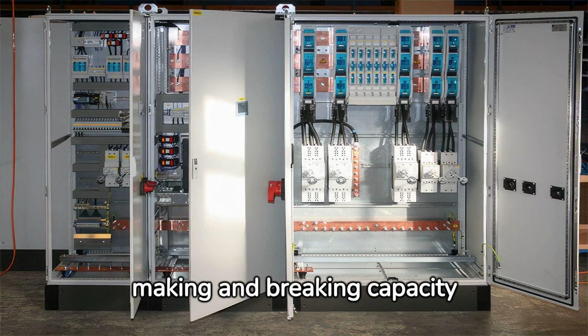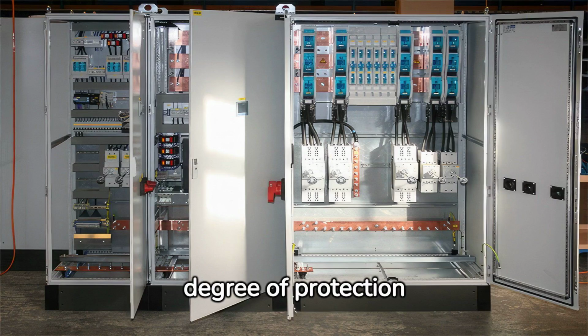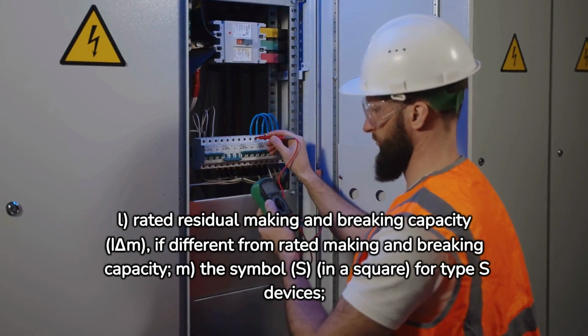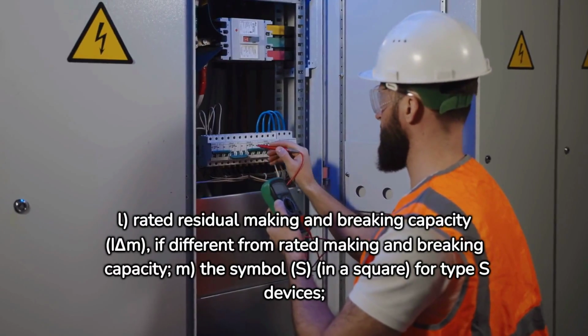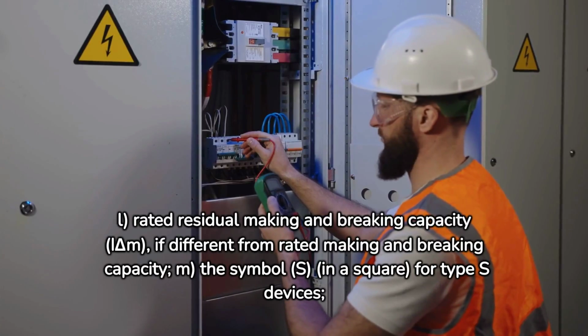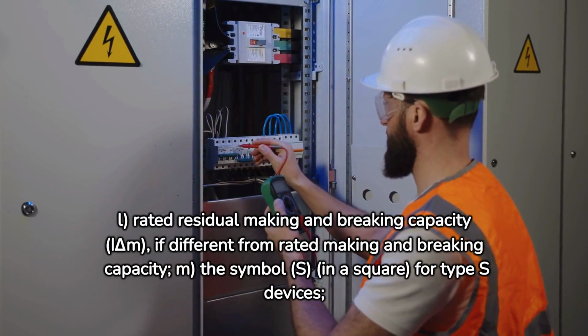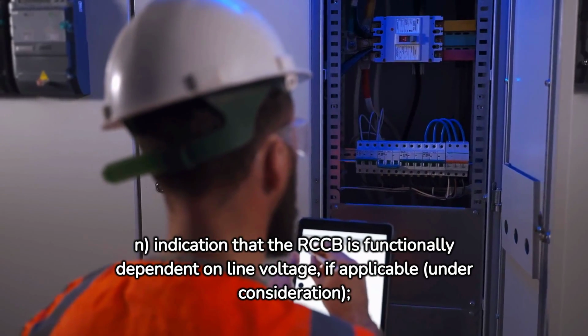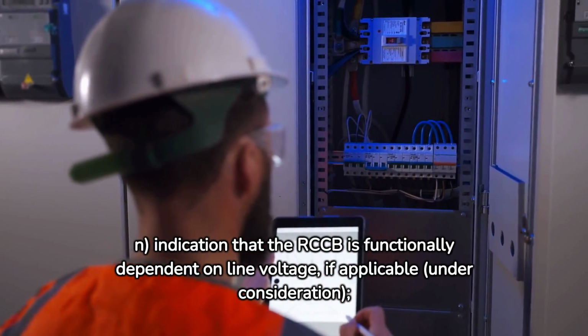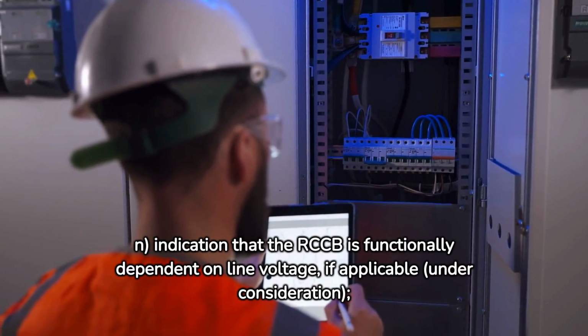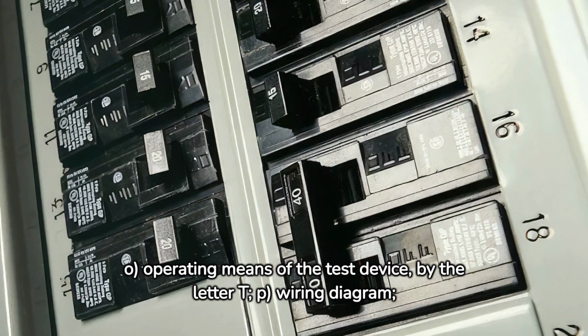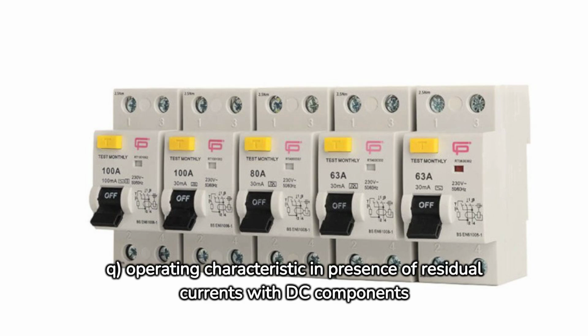G. Settings of residual operating current for RCCBs with multiple residual operating current settings. H. Rated making and breaking capacity, Im. J. The degree of protection, only if different from IP20. K. The position of use, if necessary. L. Rated residual making and breaking capacity, IΔm, if different from rated making and breaking capacity. M. The symbol S in a square, for type S devices. N. Indication that the RCCB is functionally dependent on line voltage, if applicable, under consideration. O. Operating means of the test device, by the letter T. P. Wiring diagram. Q. Operating characteristic in presence of residual currents with DC components.